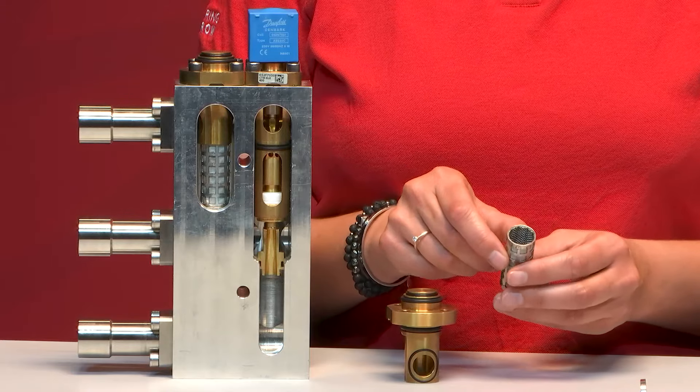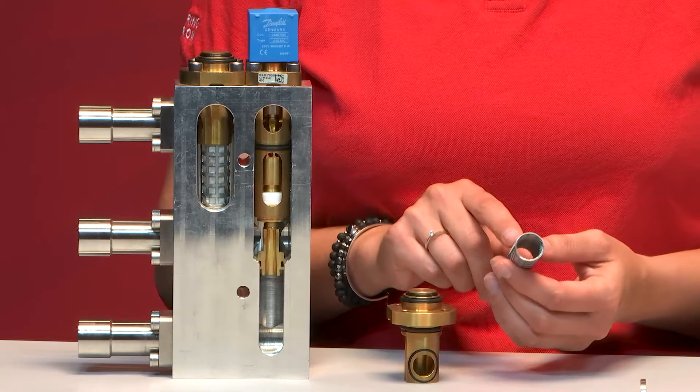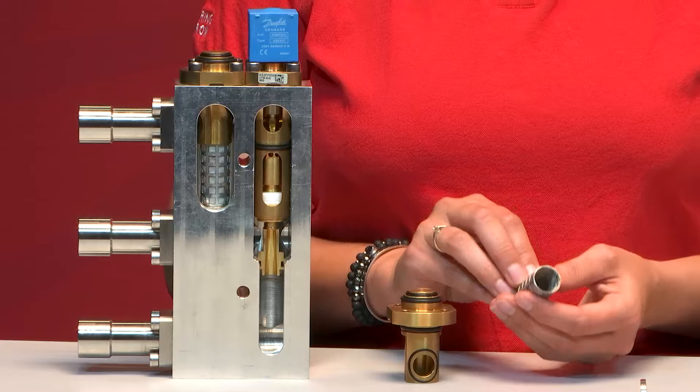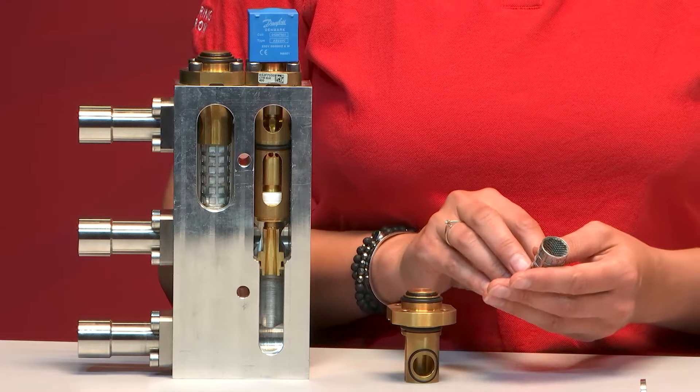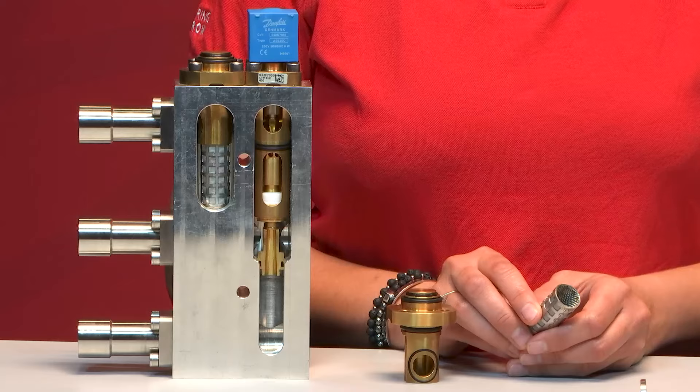When you have done service and you have cleaned it, please with your own eyes have a look and make sure the strainer is intact. Because it is very important that it is in order to protect the multi-ejector system. If it is not intact, you need to go ahead and order yourself a new service kit on our website.